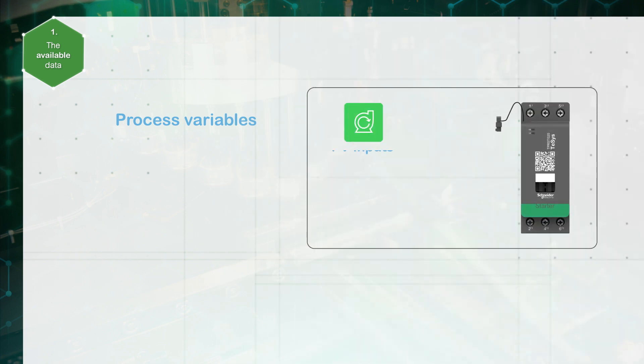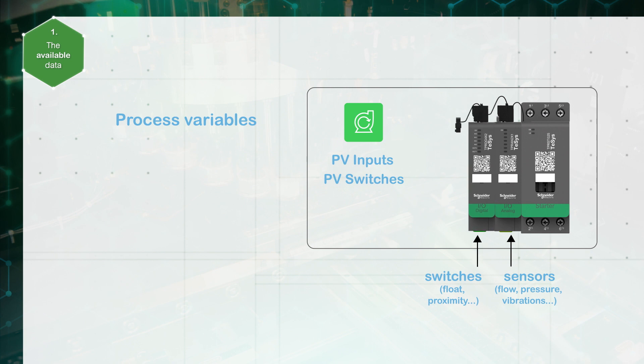To define process variables, let's consider the pump avatar. Process variable inputs receive analog values from sensors such as pressure, flow, or vibration meters — they connect to analog I/O modules included as part of the avatar. Process variable switches receive signals from switches such as float or proximity switches, and they connect to digital I/O modules included as part of the avatar.